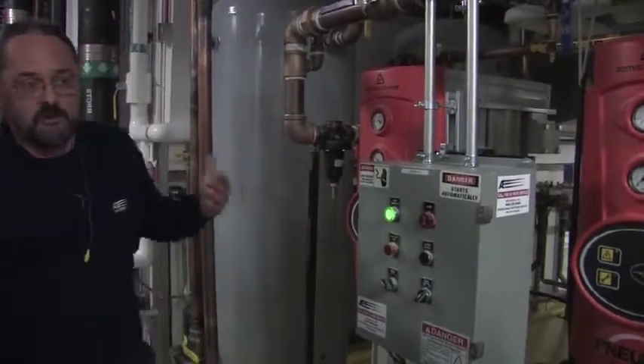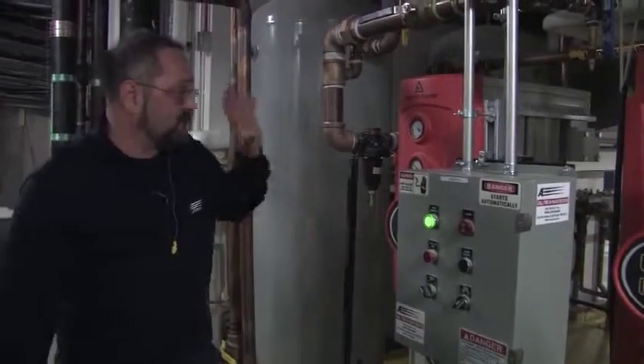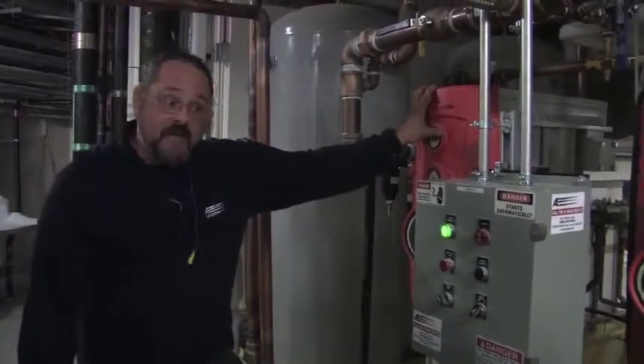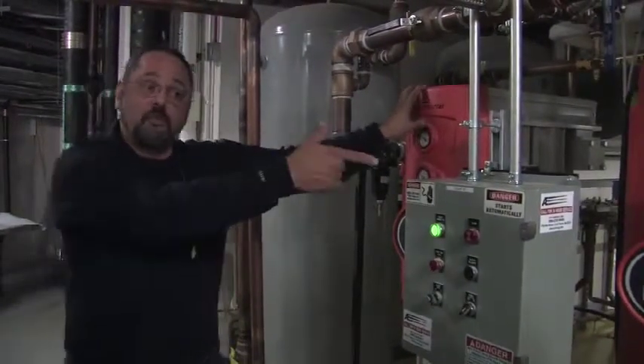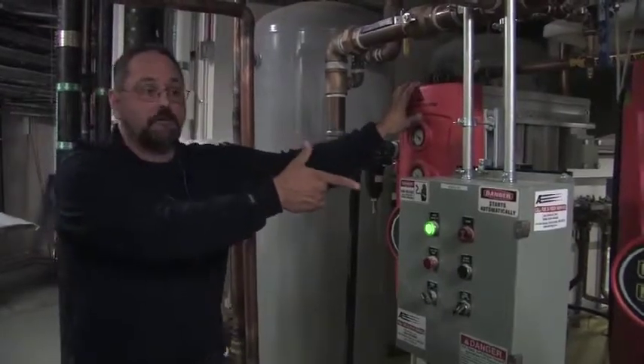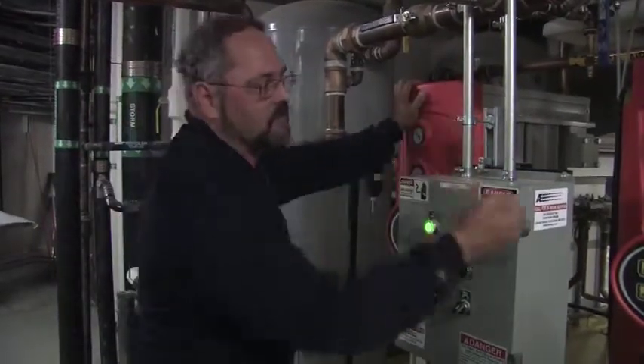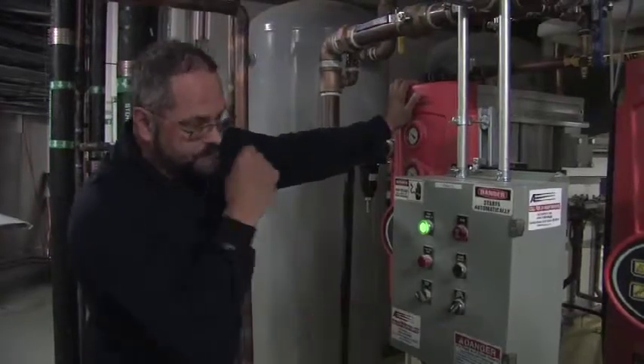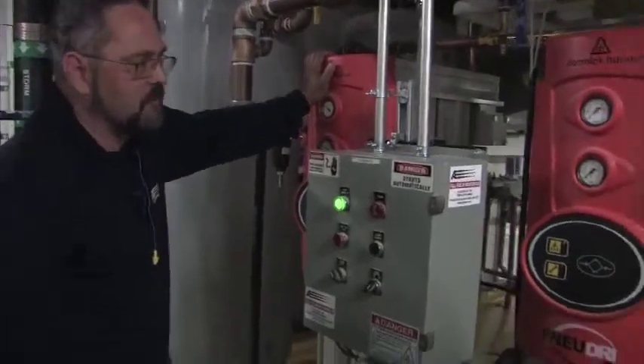But in an emergency, you're going to be putting it online in a hurry because the other one failed. So you don't want to have to wait 24 hours for this one to be good. So hence, valve them off, power them down. Now the way we power... Drain them out at all? Nope. Just valve them off, power them down.